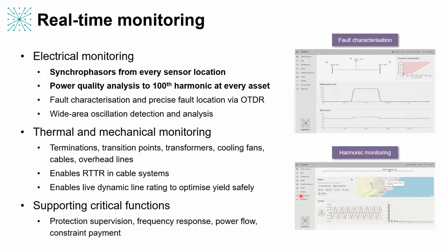In terms of interoperability, we think of that in terms of 61850, and we've shown interoperability with devices manufactured by ABB, GE, Schweitzer, and so on. And we've shown that, for protection applications, taking the whole scheme as one and doing an acceptance test of the whole scheme from tripping signals through the relay down to the super merging unit, down to the individual sensors operating over wide areas, the whole thing is completely compliant with the protection standards for accuracy, for trip times, and so on.